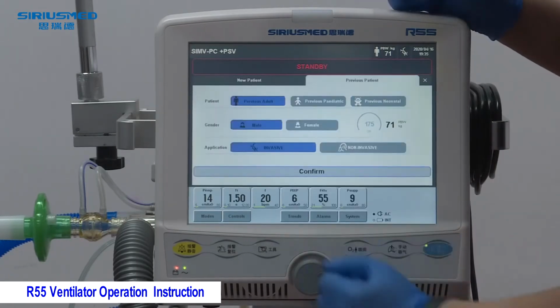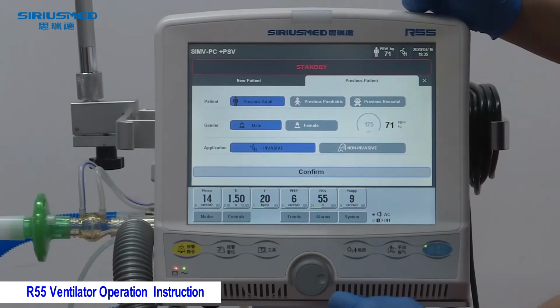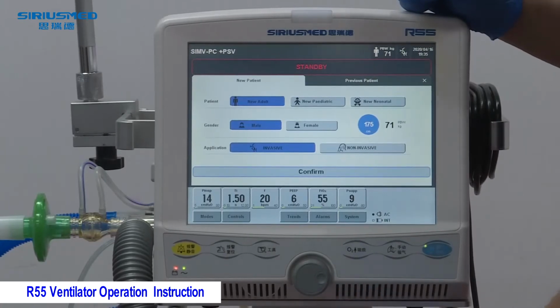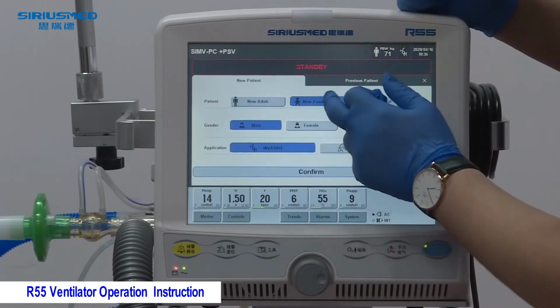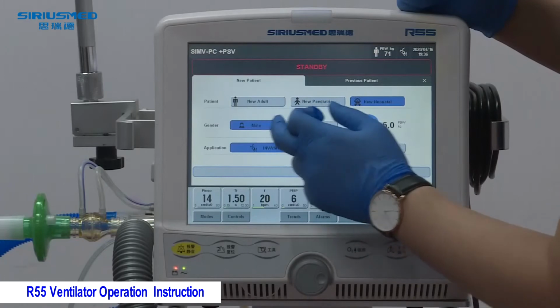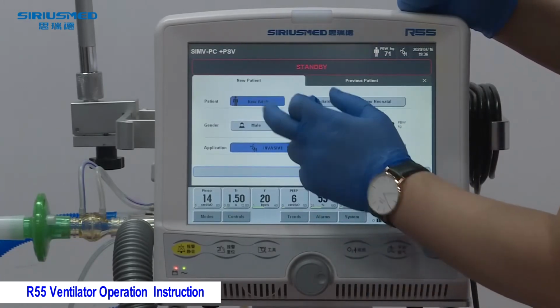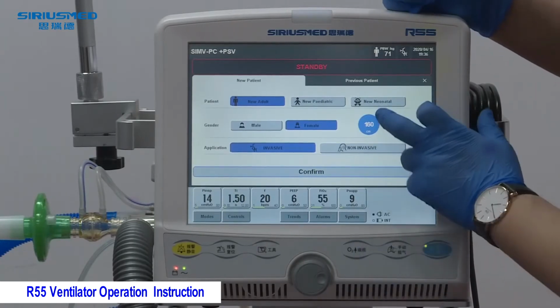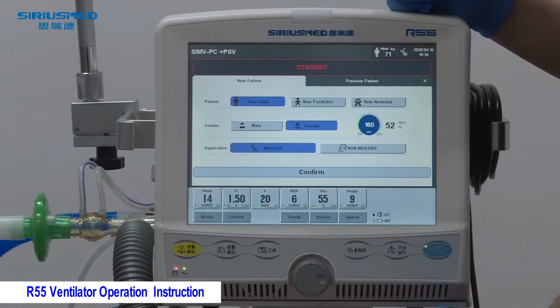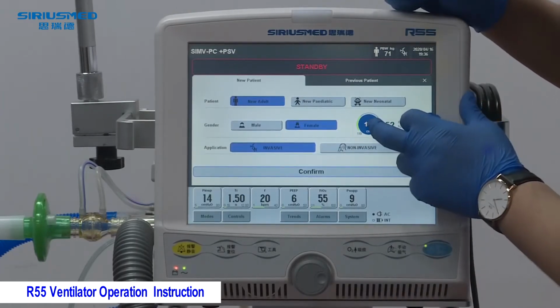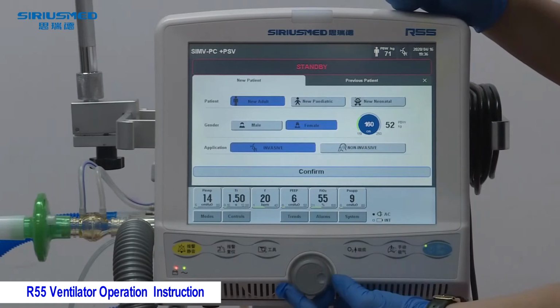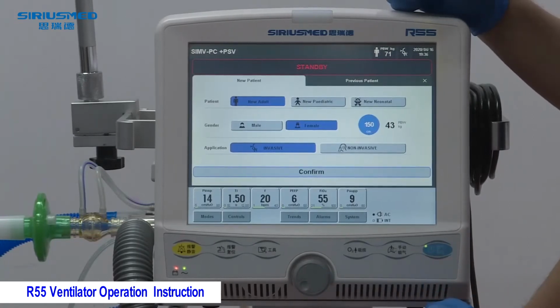There is a patient page. In the patient page, we can choose the patient information. For example, we change it to a new patient. And then, according to the patient information, we select if it's an adult, pediatric, or neonate, and if it's male or female. Then, according to the patient, we set the height of the patient. To set this parameter, first we need to select this parameter and then use the knob to change it. Then don't forget to click confirm.